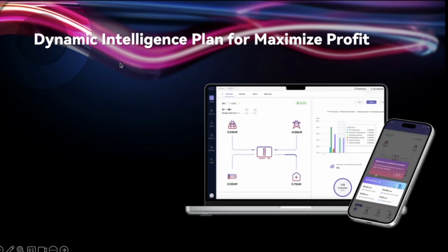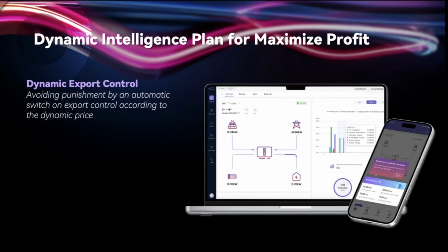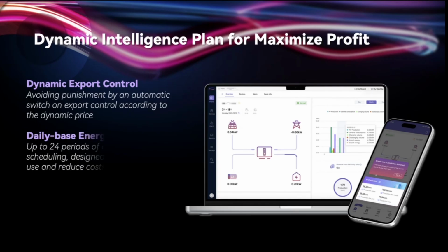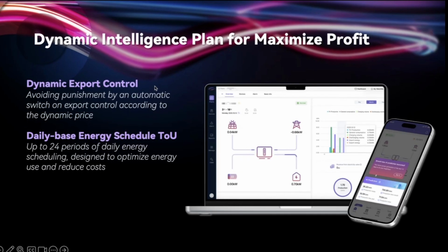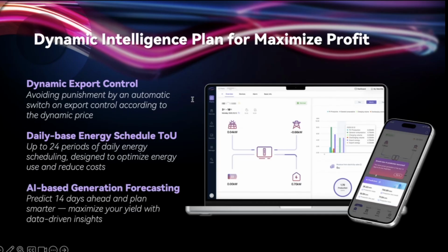And now, beyond the powerful hardware, our system also stands out in software performance, especially when it comes to intelligent energy management. First, with dynamic export control, the system automatically adjusts the export power according to grid requirements, avoiding penalties and making full use of every kilowatt generated. Next, the daily energy schedule, TOU, allows our users to set up to 24 time periods per day, optimizing energy use during off-peak and peak hours to reduce costs. And finally, our newest feature, AI-based PV generation forecasting, predicts solar generation up to 14 days in advance, helping our users plan smarter and earn more with data-driven insights.